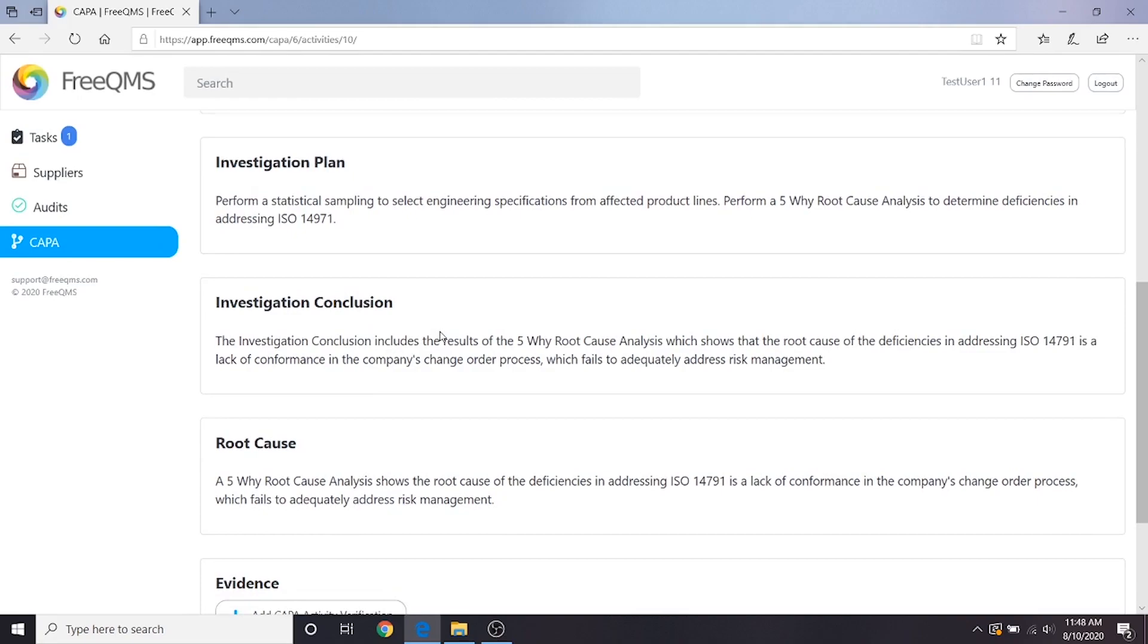In this fictional example, this means that we're processing change orders and updating specifications without considering their compliance to ISO 14971. In our fictional example, our root cause analysis has identified a likely additional corrective action that will need to take place as part of our CAPA. We need to resolve the issue with change orders to fix this problem.